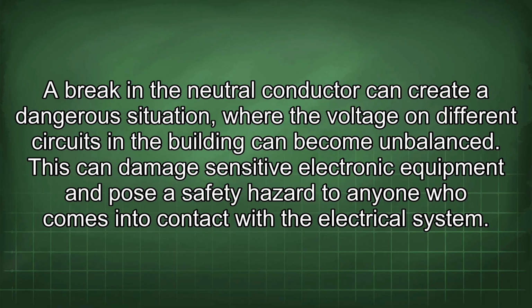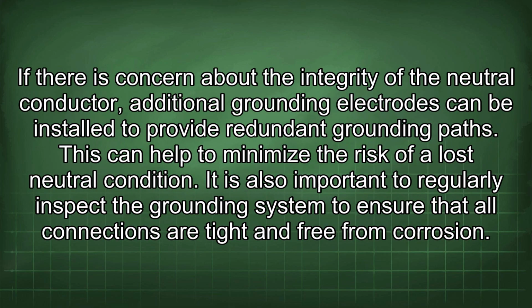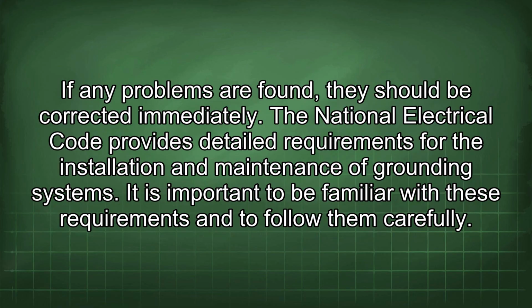If there is concern about the integrity of the neutral conductor, additional grounding electrodes can be installed to provide redundant grounding paths. This can help to minimize the risk of a lost neutral condition. It is also important to regularly inspect the grounding system to ensure that all connections are tight and free from corrosion. If any problems are found, they should be corrected immediately.